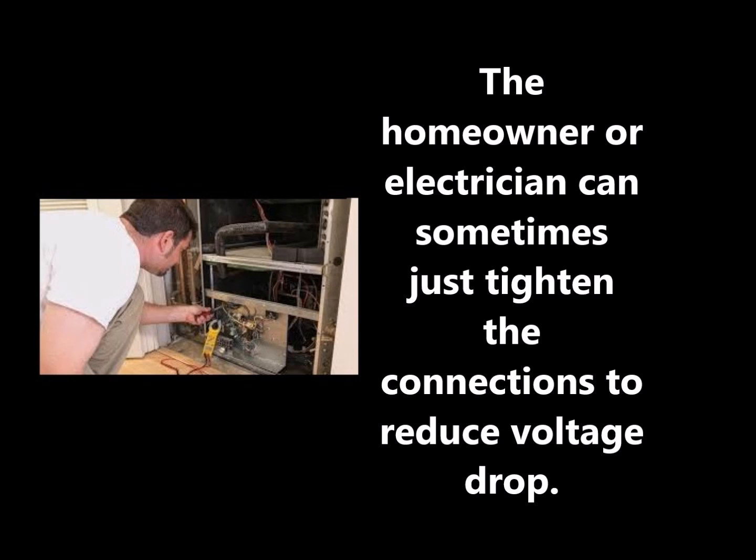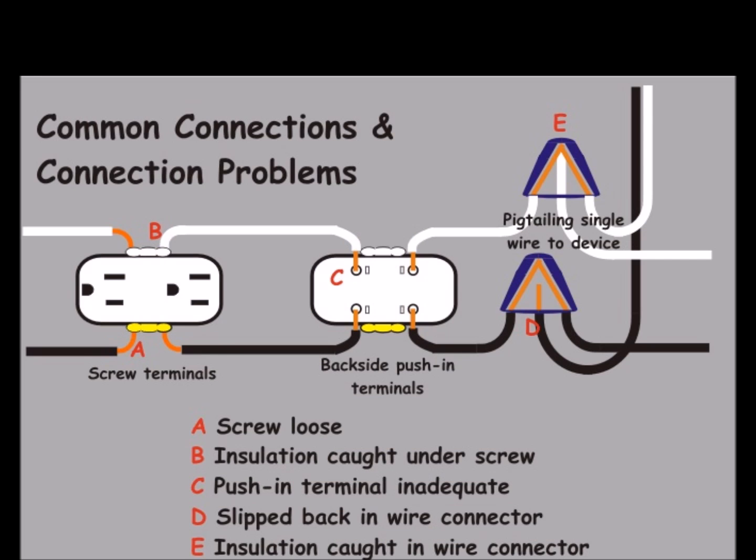Simply tightening the connections in the electric outlet might solve a voltage drop problem, but if several outlets show the same problem, then there may be a need to recommend review by a qualified electrician.